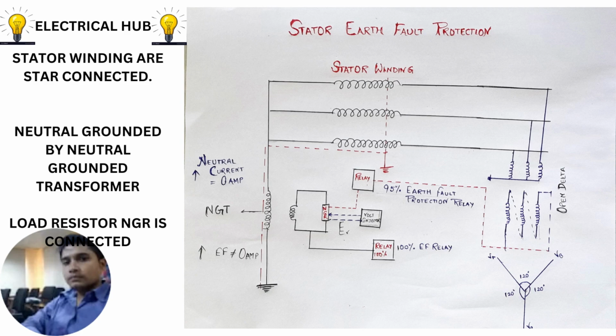From this drawing, you can understand that the stator windings are connected in star connection at the load side, which is the left hand side of your diagram. The neutral, which is going to the ground, is passing through the neutral grounding transformer, and there is also a load resistor connected with the secondary of the neutral grounding transformer.